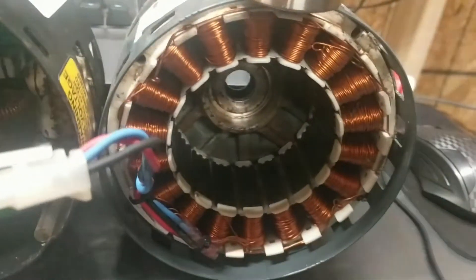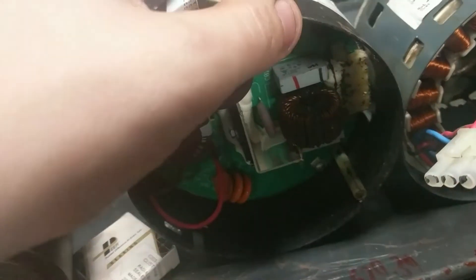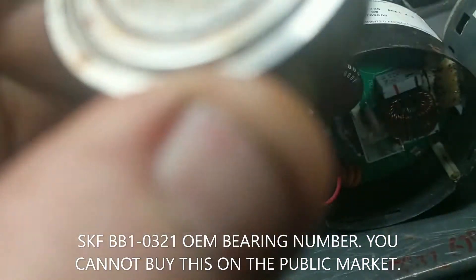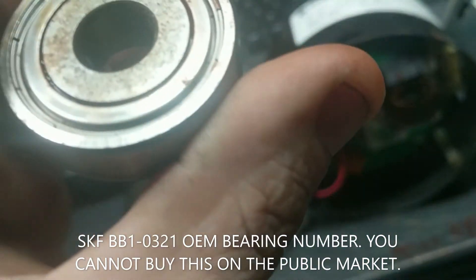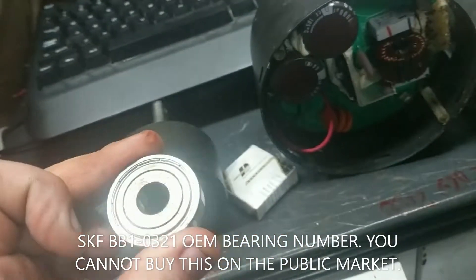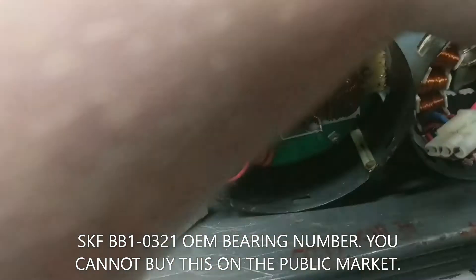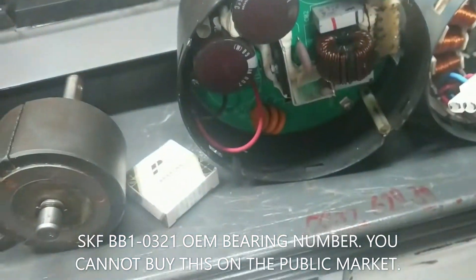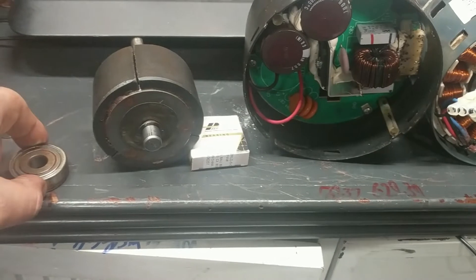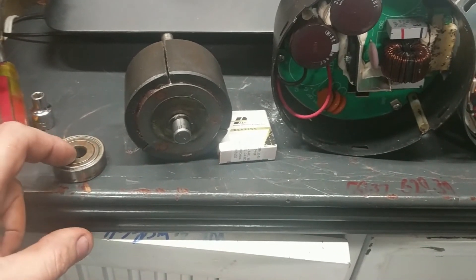It's a permanent magnet DC motor with a driver board and these SKF BB1-0321 bearings that are junk. They last about 8 or 10 years and they fail. If you go on Google or you try to go to your bearings supply place like Applied Industrial or Fastenal, they're going to tell you they can't get this bearing.